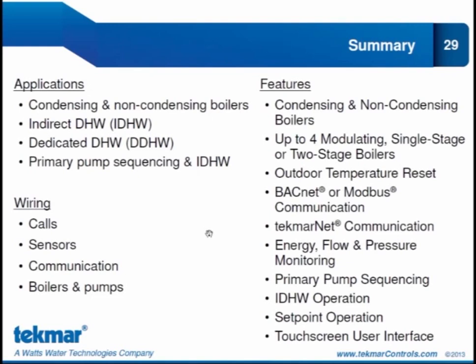So we're coming to the close of this presentation. In summary, we covered 5 applications, and those applications showed the possibilities to operate a mixed heating plant with condensing and non-condensing boilers. We also talked a lot about the indirect domestic hot water operation, so IDHW, and how we have moved away from modes, and now we configure the indirect domestic hot water based on location. Is it piped near the boiler, or is it piped on the boiler system? We'll talk about that more when we get to the technical presentation, because that selection also leads to follow-up selections on, do you want the primary pump to operate for indirect domestic hot water as well?